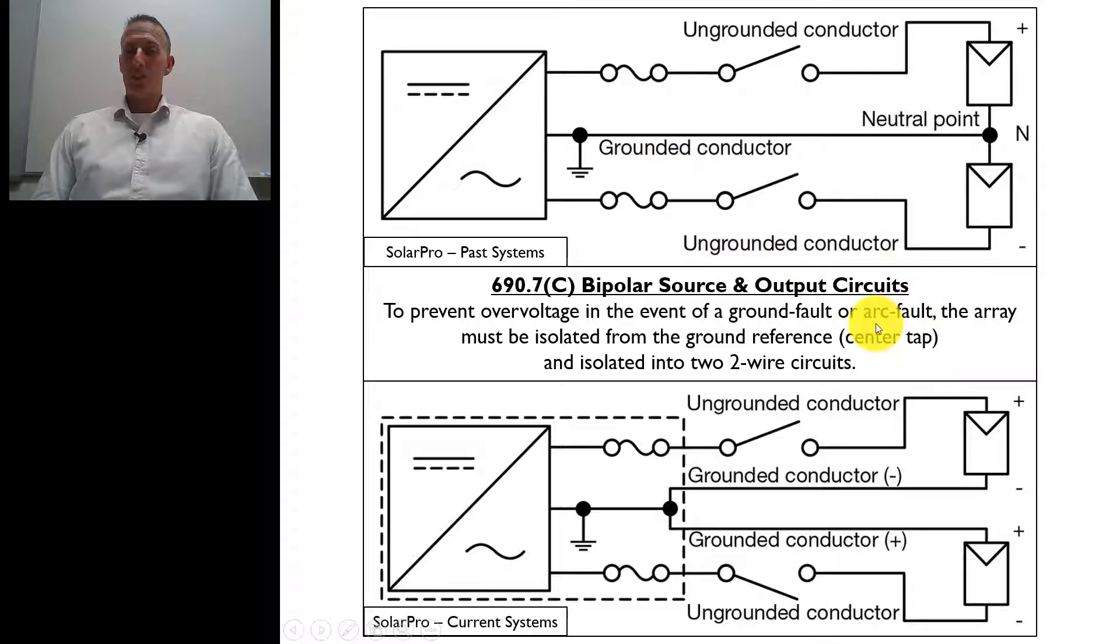What the code says is that the array, this array right here must be isolated from the ground reference center tap. So in older systems, what they typically did is they had that center tap or that neutral point, that connection, they were typically doing them inside the array.